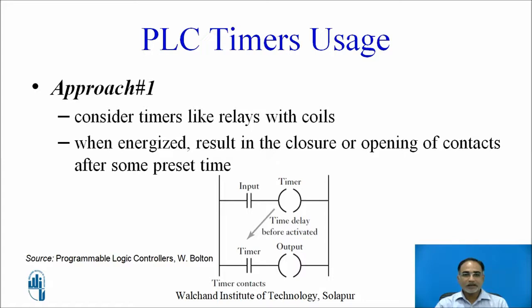There are two approaches to using timers in ladder diagram programming. In the first approach, you consider timers like relays with coils. In the first rung, the timer is shown as a relay coil symbol. When the coil gets energized, it results in the closure or opening of contacts after some preset time. In the second rung, a dependent timer contact is shown, which depends on the status of the timer. When that contact gets activated, your output gets energized.